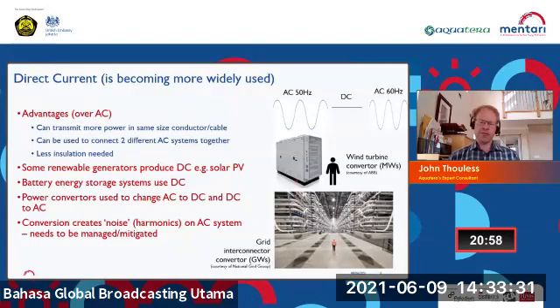The other benefit relates to renewables, certainly wind. It's best if the rotational speed of the wind turbines is linked to the wind speed. Since wind is variable, the rotational speed is variable, so the frequency at which we generate from wind turbines is variable. But if we put that through a DC link first, and then connect it to the grid, we can allow the wind turbine to operate at its most efficient while still connecting to and supporting the grid.